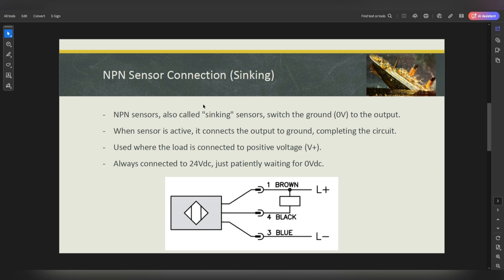When the sensor is active, it connects the output to the ground, completing the circuit. The NPN sensor is used when the load is connected to a positive voltage. The load is always connected to 24 volts, just waiting for the zero volt to happen. This is a three-wire sensor — brown, blue, black. When it switches on, the zero volt travels through the black wire and gives that load the zero volt, completing the circuit with 24V and 0V.